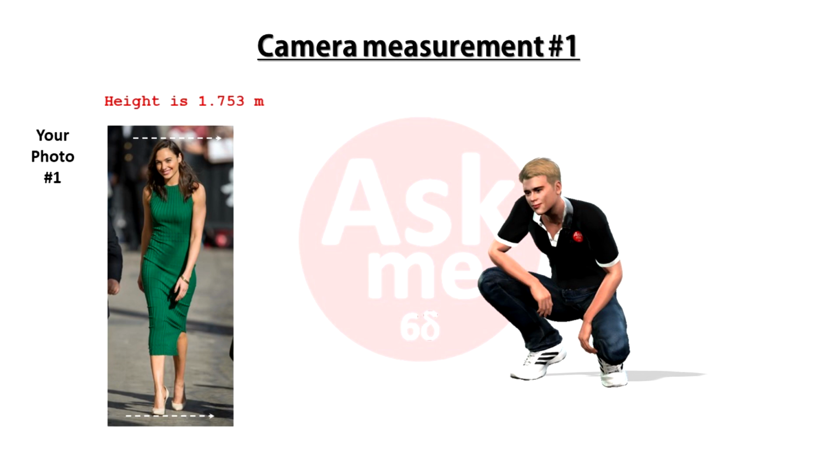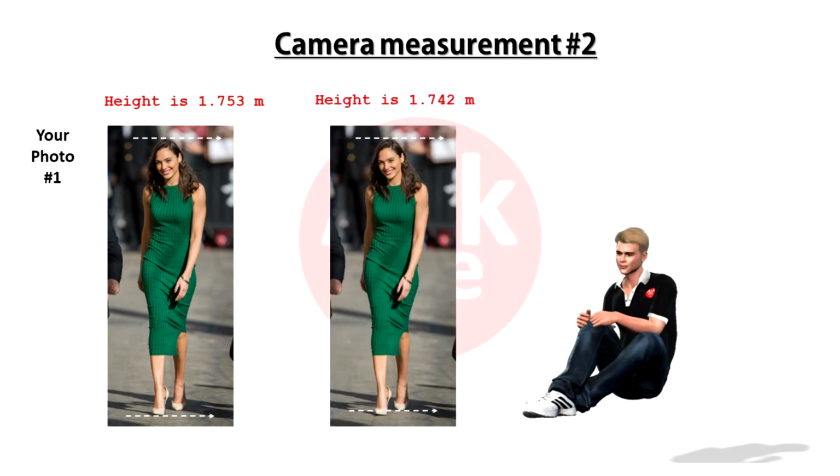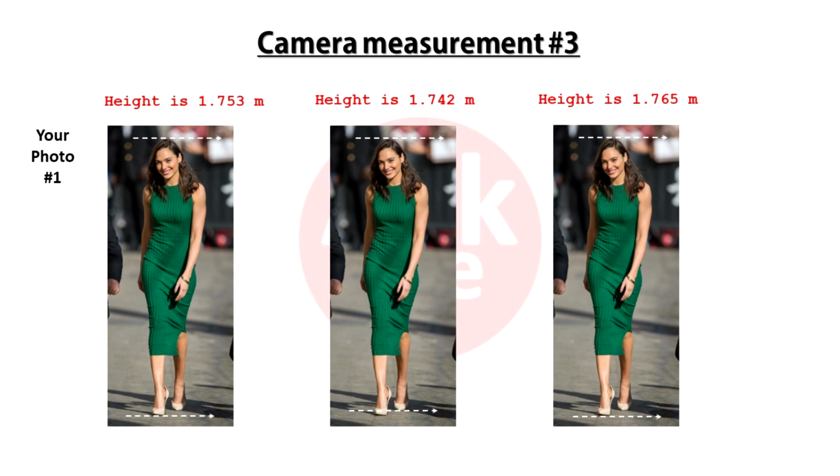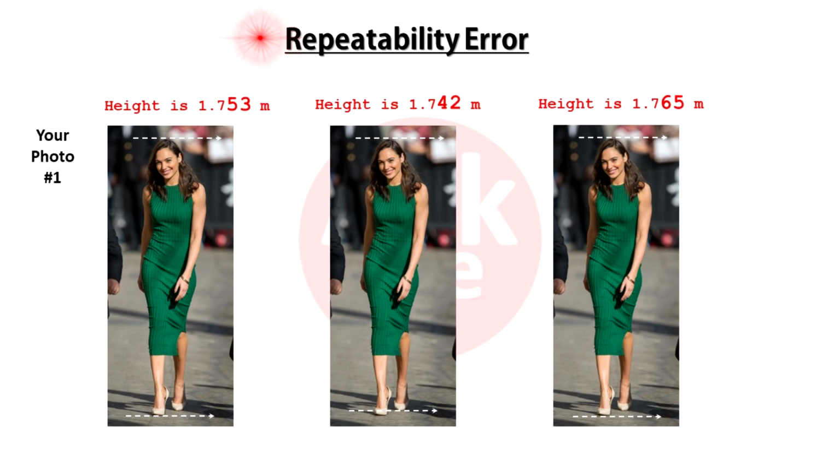Once the image is snapped, the algorithm will determine the reading from the image. How the algorithm determines the edges and calculates the reading are the repeatability error. Can the algorithm produce the same reading with the same image all the time? Those errors are repeatability errors. Combining both, you get total gauge error.